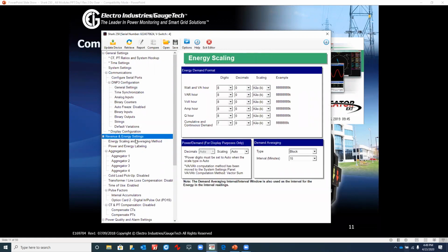We'll just jump into the revenue and energy settings real quick. We kind of skimmed through it previously, but we'll go over it again. This is where you set up the number of digits that you want displayed on the register, the decimal resolution, how many digits of resolution, and scaling: if you want kW, if the meter's in kW load or megawatt load, or if it's just watts. These are what you would choose from the drop down. And you generally set these all the same. It's up to you, but personally, I set them all at the same resolution, 8 digits, let's say 3 decimal places, and this is what it would look like on the value. So there's 8 digits overall with 3 decimal places, and it's kW. Here, if you chose M, it would be megawatts, and so on.